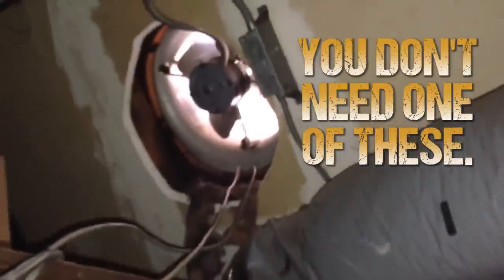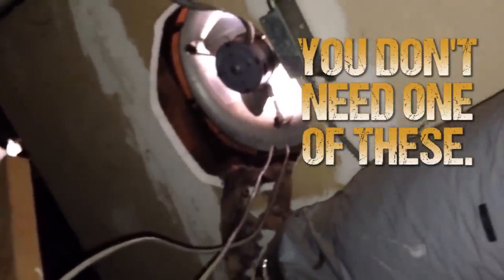Not only that, but if we take a step back we can see here is our furnace and there is an attic fan. An attic fan is really good for depressurizing an attic, which caused flame rollout, which we're seeing right over there. Very dangerous. Don't do stuff like this.